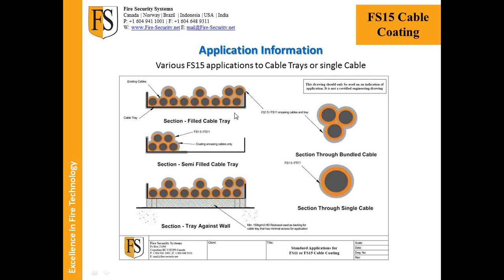Now these are 3. What you see here in the top section is the standard cable tray configuration. It could be full, it could be 60% full, 80% full, but you're effectively just encasing the external surface of that tray. If, though, you're looking at trays that are only carrying maybe 10 cables, 5 cables, then what we would prefer, if possible, is to bundle those cables to one side of the tray, with a site electrician doing that for you, and then you spray that bundle only. Okay. And the tray just below it. Top side and base, everything. Yep. So you're encasing that complete cable system.